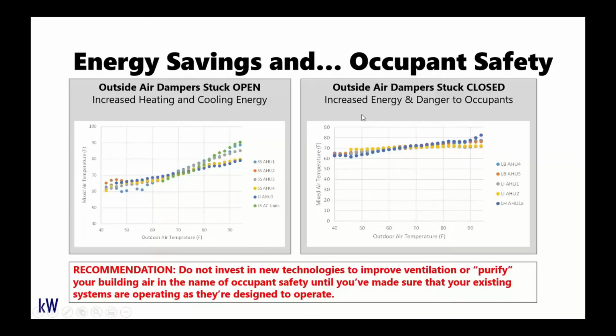Now, similarly, at the same time, and in some cases on the same buildings, we had other units that had their outside air dampers stuck completely closed. So you can see that again here from the graph. As the outside air temperature is changing throughout the course of our data collection period, there was really no associated change in the mixed air temperature. And in particular, in these mild conditions where we would expect the economizer to be functioning at full outside air mode and opening up fully to minimize the cooling consumption, we don't see any of that relationship similar to what we see here in this data.